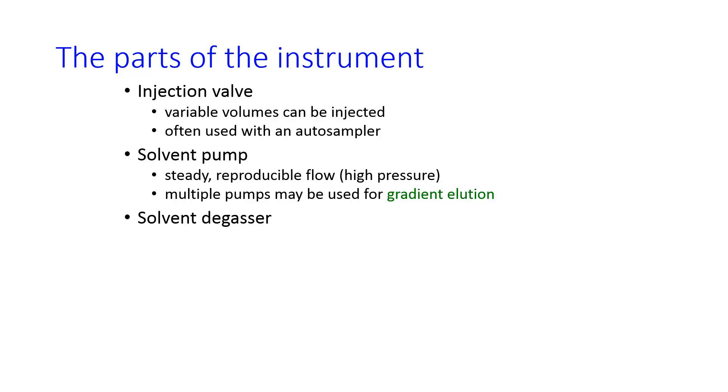The solvents, before they hit the pump, go through a solvent degasser, and the idea of this is to remove dissolved gas, because that dissolved gas makes high-pressure, reproducible flow really difficult. It's much easier to pump a liquid than it is to pump a gas with constant flow.